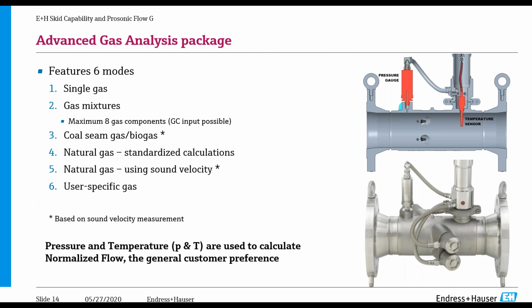And so we see here, this gas analysis package has 6 different modes. We can also do single gases, so that's easy. What we can do is gas mixtures of up to 8 different components. So when we do the corrected volume flow, we're doing all those compressibility factors for all those gases. It's also able to do this dynamically with our Modbus option. And we have what we call our coal seam gas biogas. We're quite experienced, especially in biogas and coal seam gas, with doing a gas analysis.